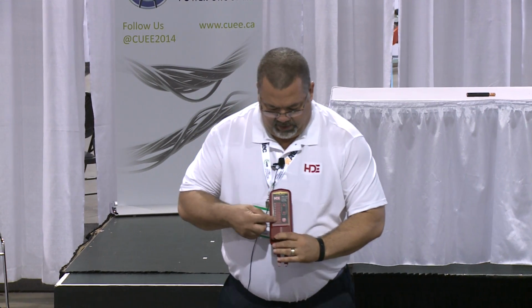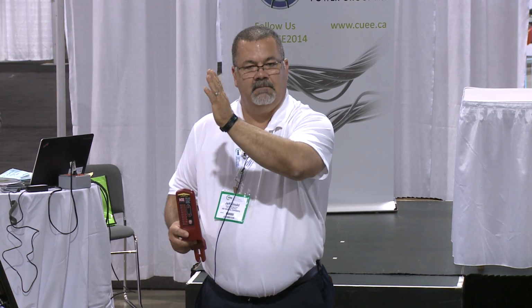So as I use something like our PRX 500, if I were on a 69 kV, I would select the 69 kV range, and then I'm going to detect voltage at about 8 to 10 inches, which gives me that flexibility in that electric field measurement to say, okay, phase A is energized, phase B is energized, but phase C is offline. So what I've done is effectively shortened that detection distance to where I can make some critical decisions in a confined space.